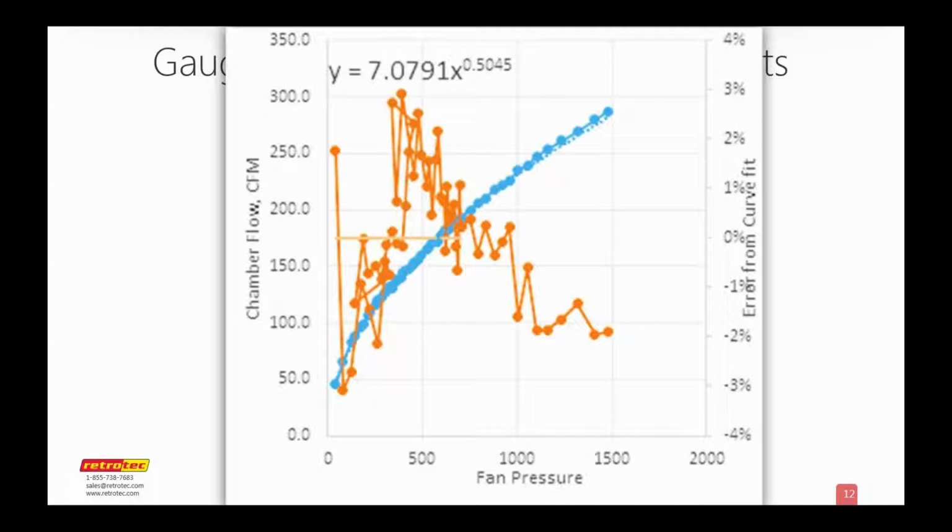It's actually the shape of an elliptical orifice, which I'm sure not too many of you have got one of those. The DG700 also has leakage area. They don't really define which ELA it is. I'm pretty sure it's EQLA as well. So you can get square inches on that as well.